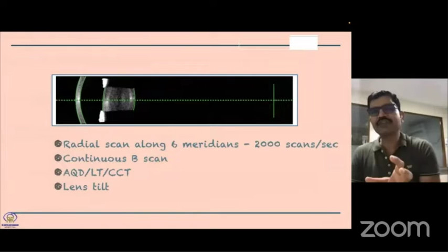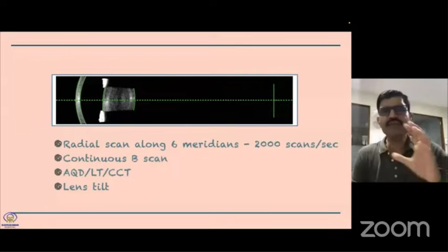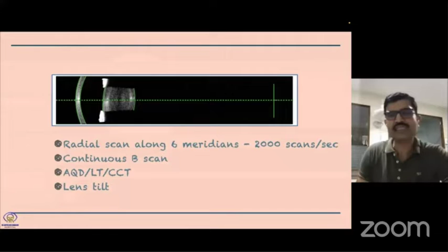This machine, the prototype machine, scanned the eye into six different radial meridians along 0, 30, 60, 90, 120, and 150 degrees. Each meridian was scanned 5 times to give us 2000 scans per second, and it gave us a continuous B-scan picture wherein we can calculate any point to any point in terms of millimeters. It also gave us AQD, lens thickness, and central corneal thickness, and it also gave us clues regarding lens tilt whenever it is present. By looking at the actual placement of the lens in the B-scan, we can know that.